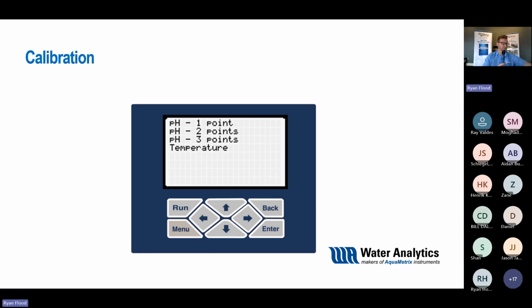So as soon as you've got your sensor plugged in, you'll put it in, and then you'll go to your choices here of auto calibration or manual calibration. For the sake of this demo, I'm going to go through the auto calibration, really to highlight just how simple this is going to be. Your manual calibration is going to be very similar to the auto calibration. It's just going to give you a little bit more flexibility in terms of choosing what standards you have. Again, as I referenced, we have 4, 7, and 10 as our standards. Some people prefer 9, some people prefer 6. Again, for most of the industry, 4, 7, and 10 are your standards. Auto calibration knows that, and it actually has some ability to detect which solution you're putting it into as a reference solution. Manual calibration will just remove that and you'll manually enter it in. So it's a little bit slower, but only by a few seconds.